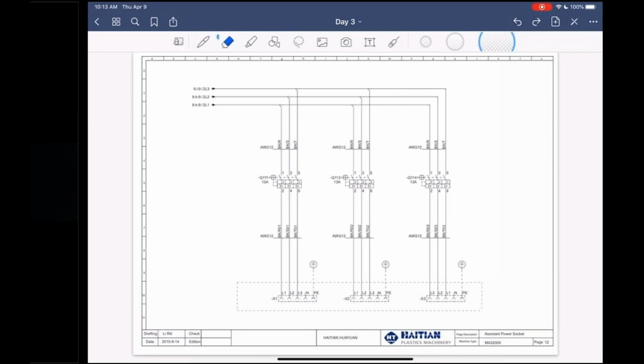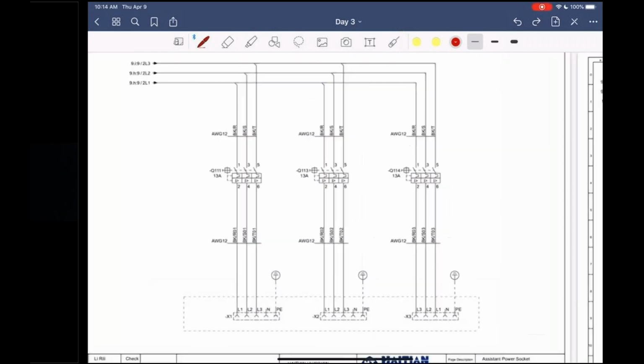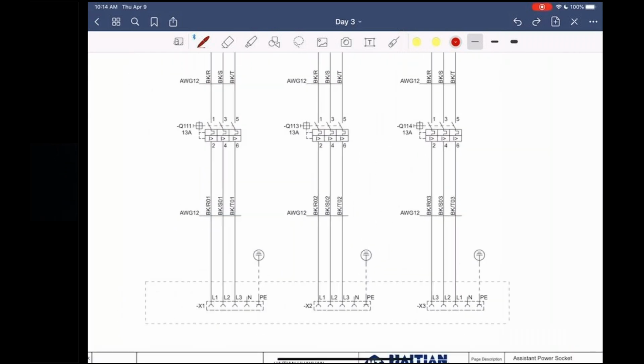The next page is the assistance power sockets. Again, there's 3 sockets on the back of the machine. It's a black box, and it has 3 faceplate covers on it. So it has little square covers with 4 screws, and that is not calculated in the full load amperage of the machine. So if you're to use those, make sure that your amperage going to the machine is adequate enough to handle the 3 sockets that are on the back of the machine. So therefore, you'd have to add 3 13 amp circuits, which is 39 amps extra.